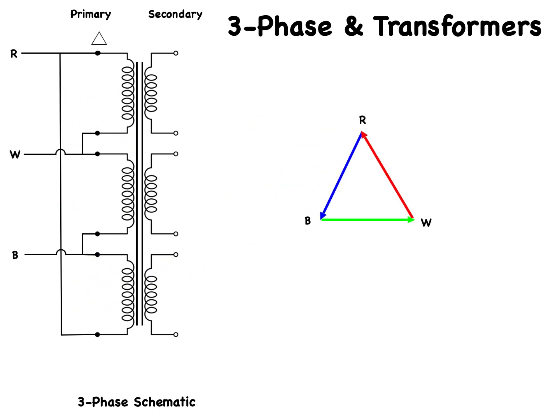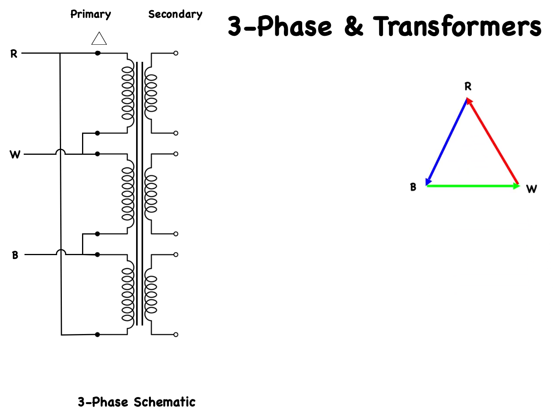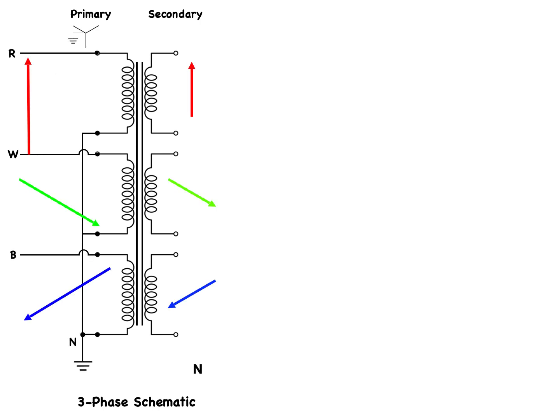Because we have connected the terminals of the primary windings together, we can move the phasors anywhere on our two-dimensional slide; however, they are pinned — if you move one phase, all the rest have to move likewise. Let's now look at the secondary side of the transformer and how it can be connected. Let's start with a grounded Y connection on the primary and connect the bottom side of all the windings on the secondary side — in other words, make an ungrounded Y connection. Note that the voltage across the winding on the secondary side is always in phase with the voltage on the primary side winding of each transformer, because they are magnetically linked to each other.